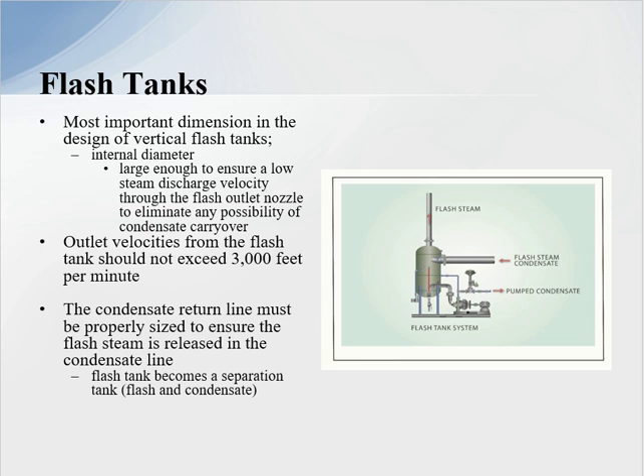Outlet velocities from the flash tank should never exceed 3,000 feet per minute. The condensate line must also be properly sized to ensure the pressure flashing occurs in the condensate system.